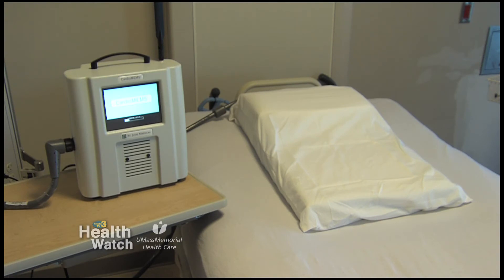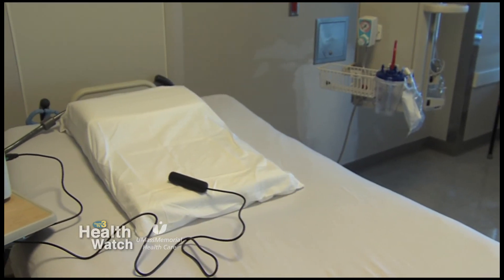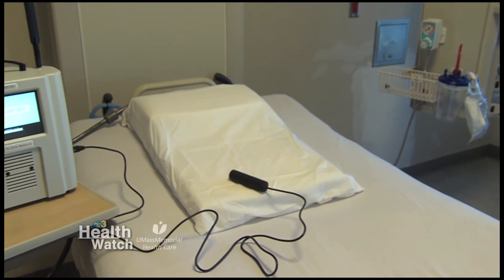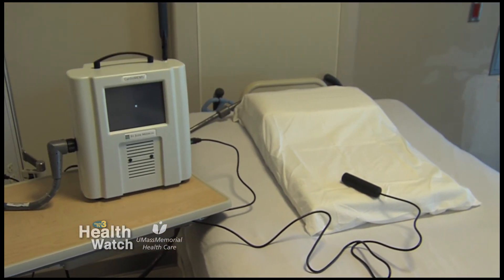The device is very simple, has a couple of components, and does not include a battery. Instead it has a partner in this pillow that includes an antenna that sends a pulse to energize the device, take a pressure reading from the patient's pulmonary artery, and send it through a landline or a mobile phone connection to a central monitoring website. We can get a reading of the patient's pressures on a daily basis — it takes just 18 seconds to get a reading.